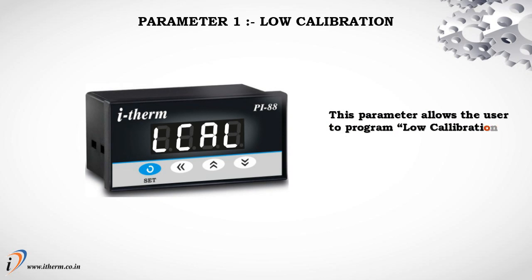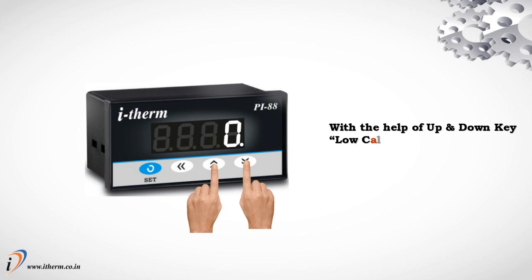Parameter 1: Low Calibration. This parameter allows the user to program low calibration values other than the factory low calibration values for the selected input type. With the help of the Up and Down keys, the low calibration can be adjusted. Parameter 2: High Calibration. This parameter allows the user to program high calibration values other than the factory high calibration values for the selected input type. With the help of the Up and Down keys, the high calibration can be adjusted.